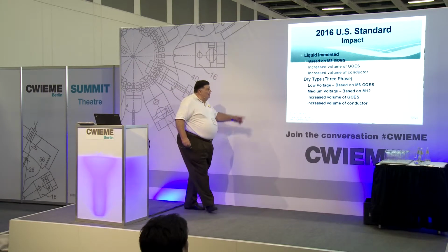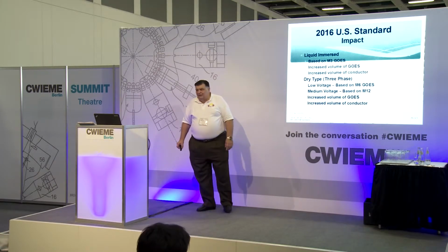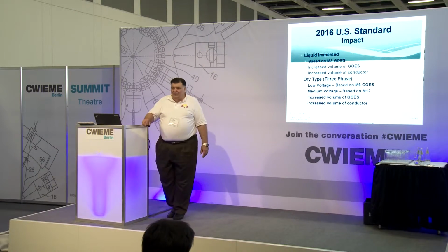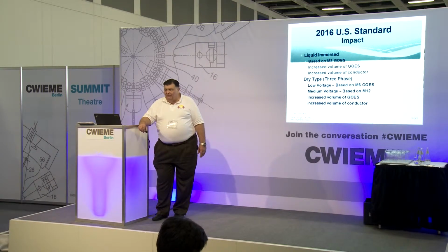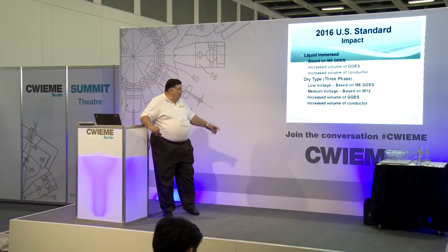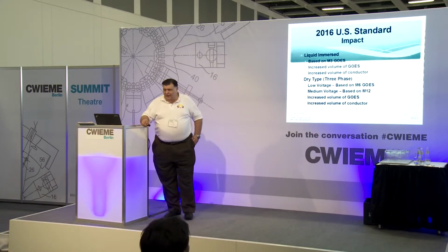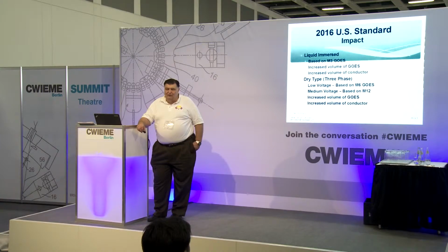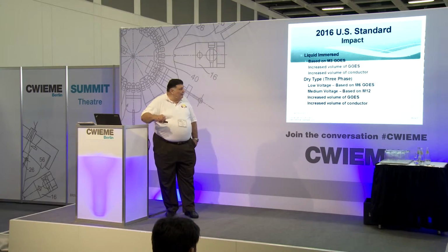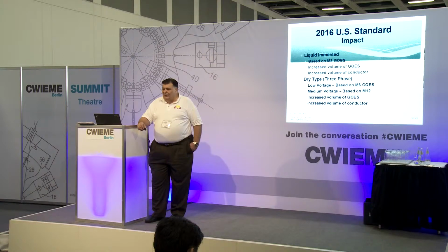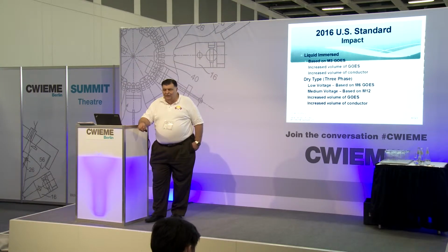What does that mean? For liquid immersed, M3 electrical steel is the base. Anything below an M3 grade of steel will not be viable on liquid immersed. There will be an increased volume of grain-oriented steel. An 8% decrease in losses is about a 10% increase in the mass of the core, using M3 as the base. And an increased volume of conductor. With M3 as the base and an 8% decrease in losses, the coil assembly will go up by about 15%, and that's still assuming copper in the high voltage and aluminum in the low voltage.